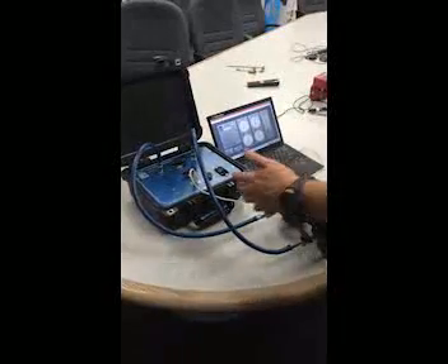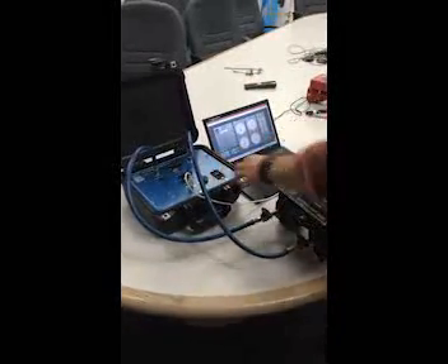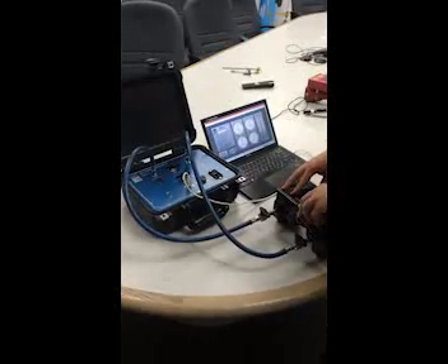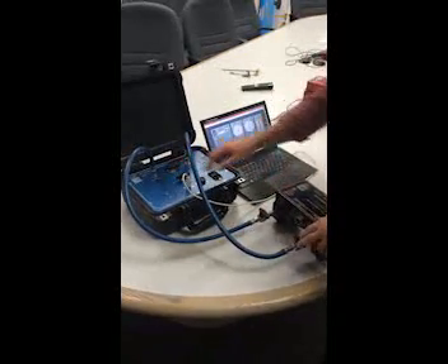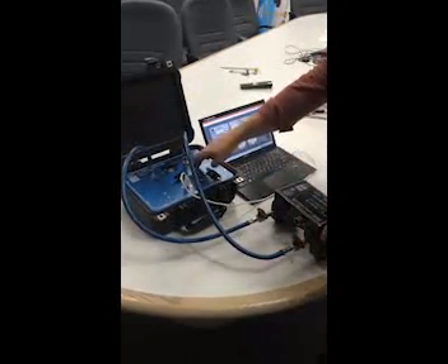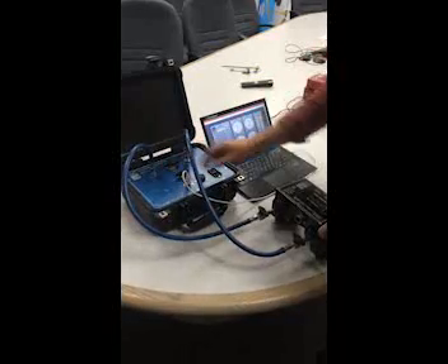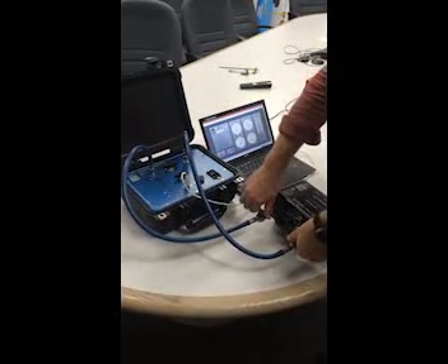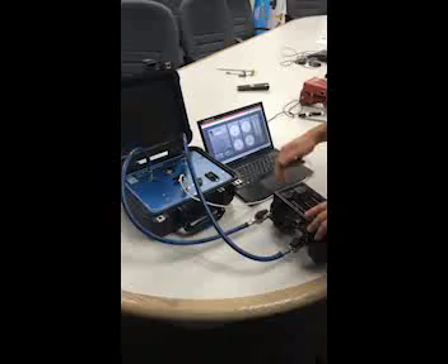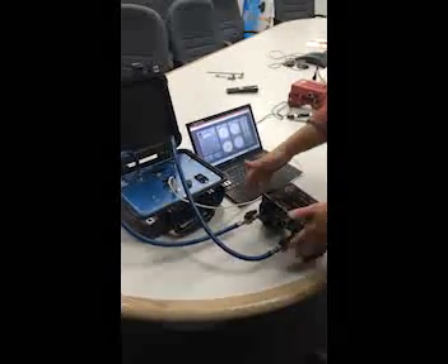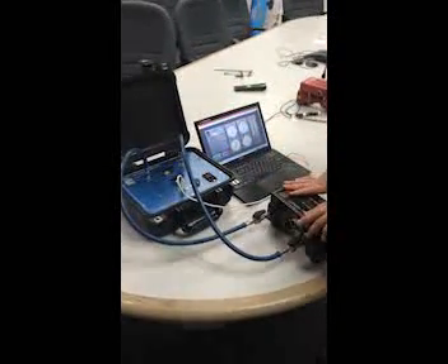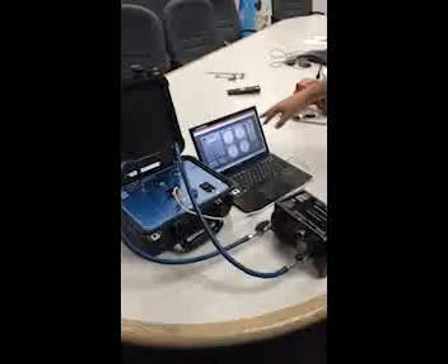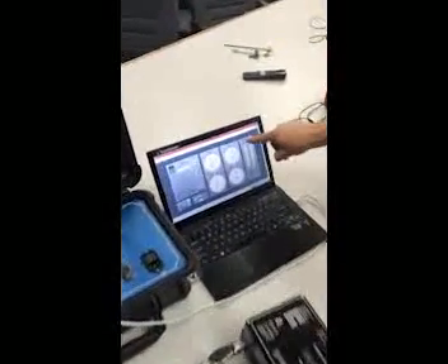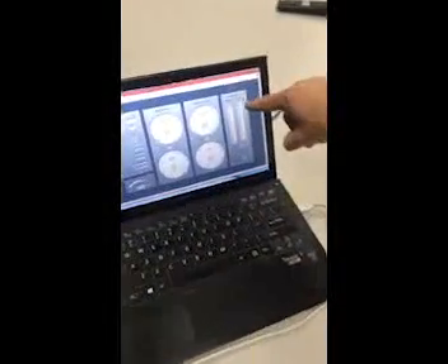Now that we have our hoses connected correctly between the FM50 test set and the FM50, we want to make sure that we open up all 4 valves. In a previous step, we opened up the test set valves, so verify those are still open. We will open up the ball valves here on the FM50. This will allow the natural gas to go from the FM50 into the test set. Once you've done that, if you look on the right-hand side of your screen, you're going to see the gas temperature for the test set, which will be the very far right-hand side.